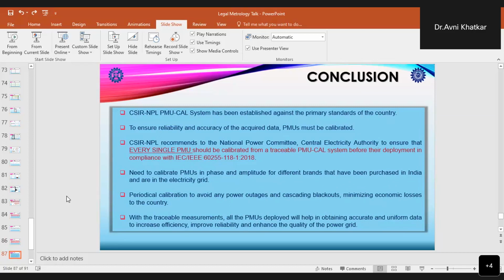And we need to calibrate PMUs in phase and amplitude from the different brands that are being purchased in India and are in the electricity grid. Periodical calibration should be done in order to avoid any power outages and cascading blackouts, minimizing economic losses to the country. With these traceable measurements, all the PMUs which are deployed will be helpful in obtaining accurate and uniform data in order to increase efficiency, improve reliability, and enhance the quality of the power grid.